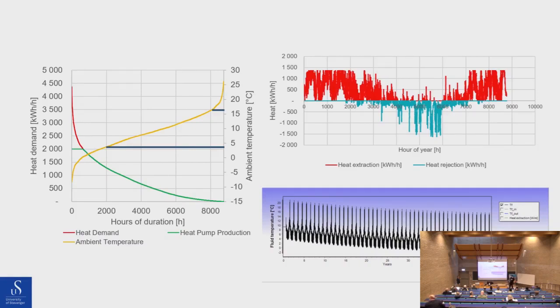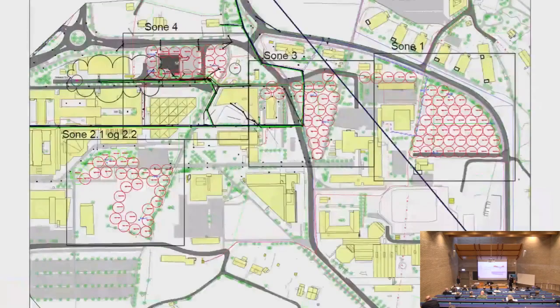So we're working a lot to find this balance so that this type of curve will balance itself out even more than it does today. And of course, the higher the temperature is in the ground, the more efficient the heat pump process is, but still we achieve a COP now of about 4, so you get 4 times the amount of energy that you put into the heat pump.